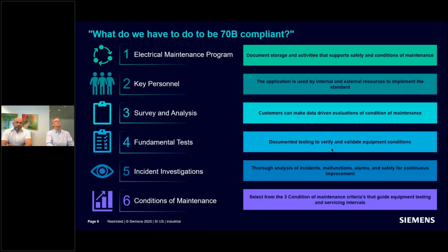The other thing is, if you read through the standard or take a training program in it, you'll find there's a number of surveys and a lot of analysis that has to happen with those surveys. Some of them you're probably already doing, so there's some overlap. It requires an arc flash study, for example. One thing that was kind of new to the organization I worked with is that now load flow studies were required every 5 years, things like this. So it started looking like all these things became quite burdensome.